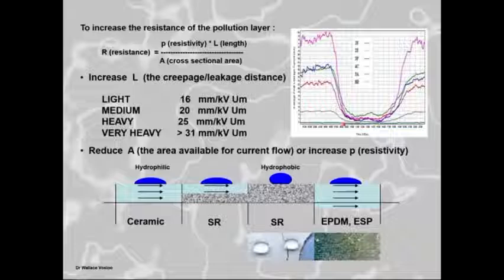You can see this is the data we got on silicone rubber, EPDM, porcelain, coated porcelain, cycloaliphatics, and resistive glazed insulators. Resistive glazed insulators work excellently, but they're not so good for a cold switch on, and that's when you get your flashover problems. But you can see when you take a look at your levels here, you'll see that your silicones and your coated silicones are doing very well, and your cycloaliphatics are really poor. And you can see your porcelains and your EPDMs. You can see that at times the EPDMs are worse, and it's because of this phenomenon which we're seeing here.